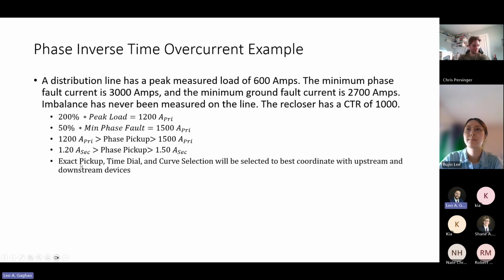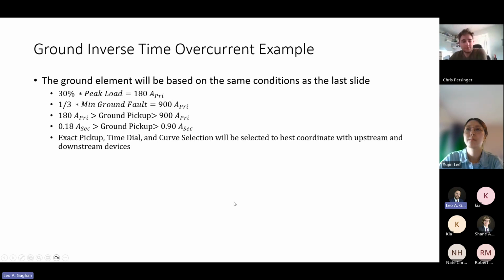So after you find that acceptable range, your exact pickup, time dial, and curve selection would be best selected to coordinate with upstream and downstream devices. Ground, in the interest of time, we'll probably skim over. It's very, very similar, except you've got different margins. Same exact goal. The only difference is that rather than operating on phase current, you're operating on ground current. It's just usually more sensitive, because peak ground current based on imbalance is usually much less than peak phase current.